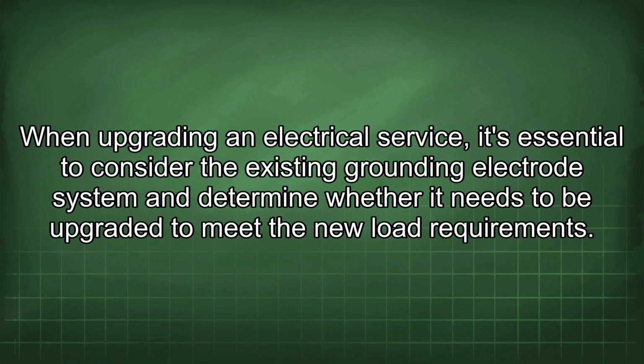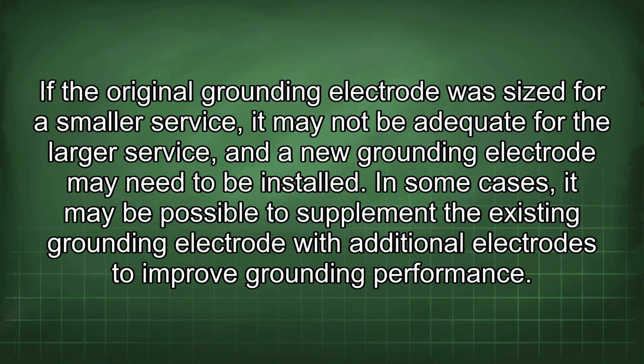When upgrading an electrical service, it's essential to consider the existing grounding electrode system and determine whether it needs to be upgraded to meet the new load requirements. If the original grounding electrode was sized for a smaller service, it may not be adequate for the larger service, and a new grounding electrode may need to be installed. In some cases, it may be possible to supplement the existing grounding electrode with additional electrodes to improve grounding performance.